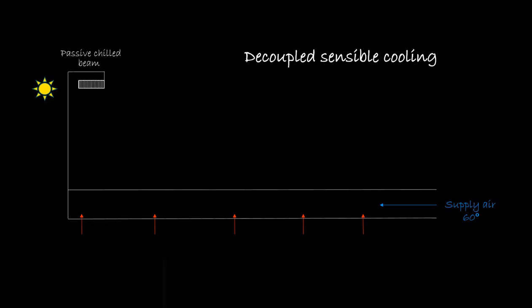The coil in a passive beam uses chill water delivered at or above the room dew point temperature to assure that no moisture is removed and thus no condensation occurs. Convective air currents flowing along the perimeter walls and windows travel through the beam's coil where sensible heat is removed.